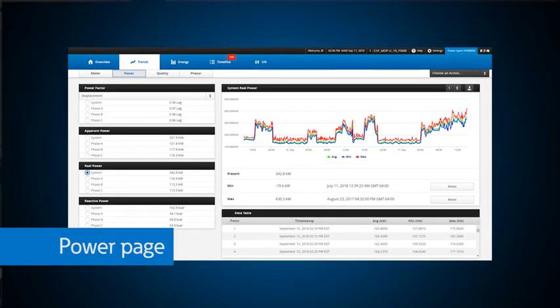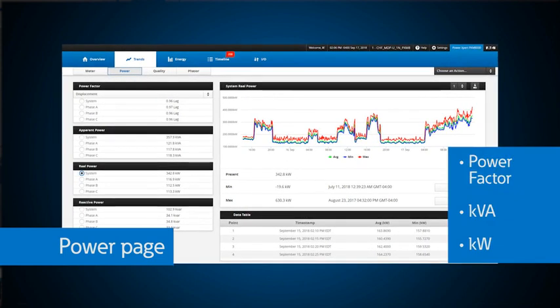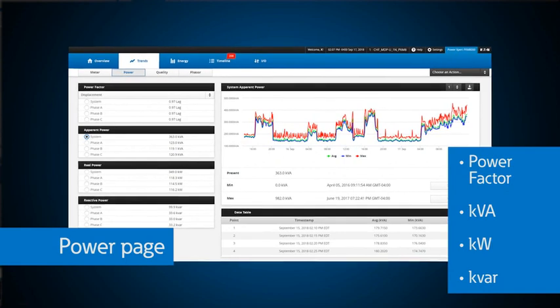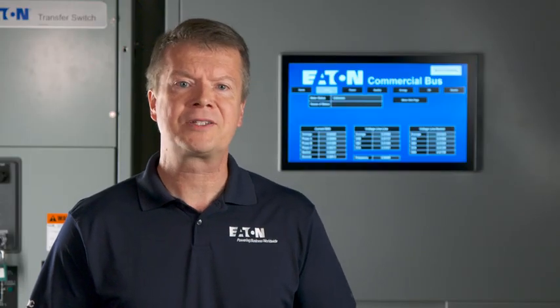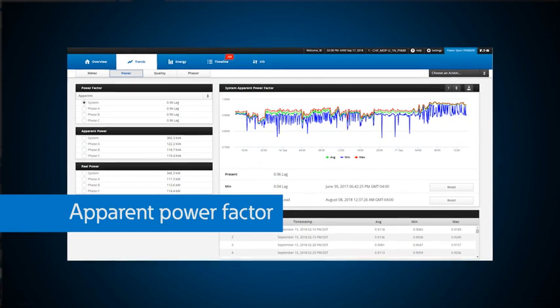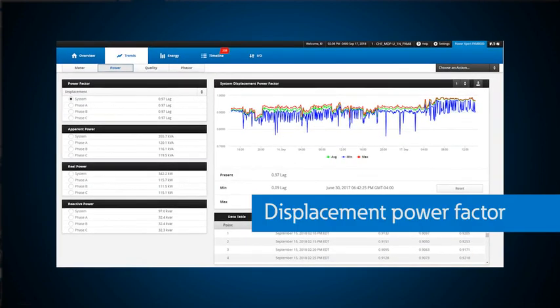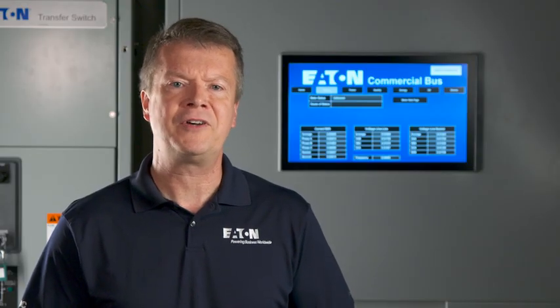In addition, on the power page, you can view and trend power factor, kVA, kilowatts, and reactive power per phase or as a three-phase roll-up. The meter can display power factor with harmonics, also known as apparent power factor, or will display displacement power factor, which is what utility companies' bills are based on. Displacement power factor is only calculated using the fundamental, or here in North America, the 60 Hz part of the voltage and current.